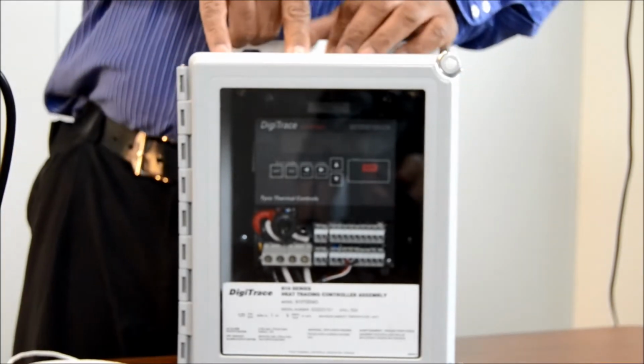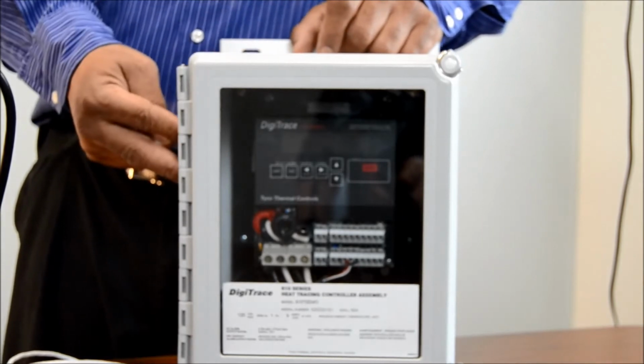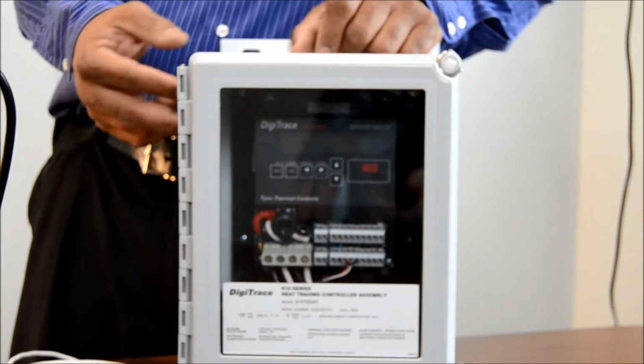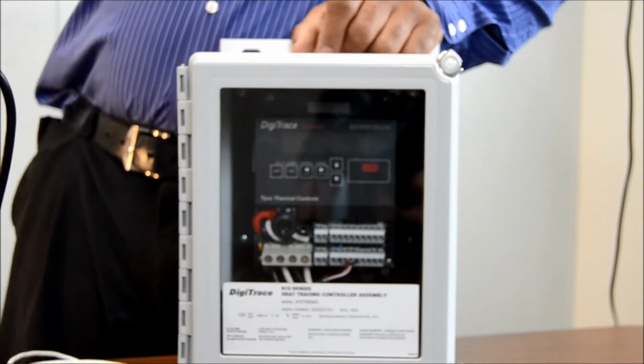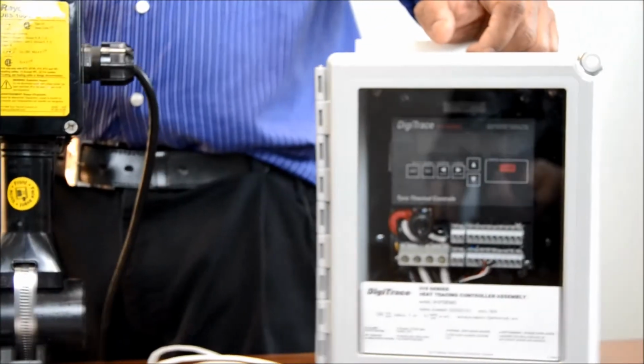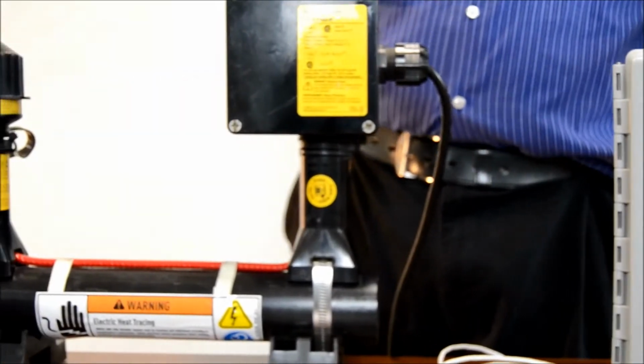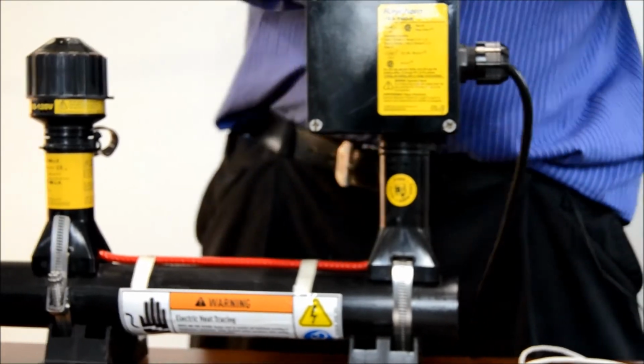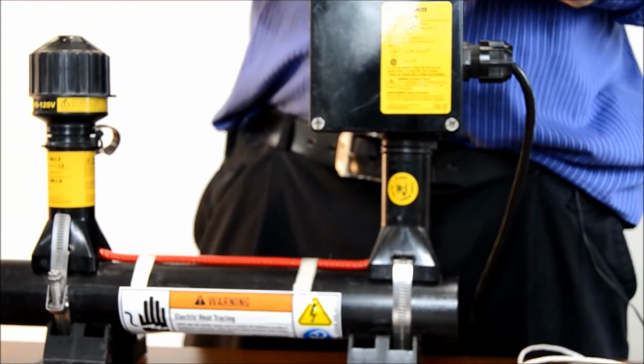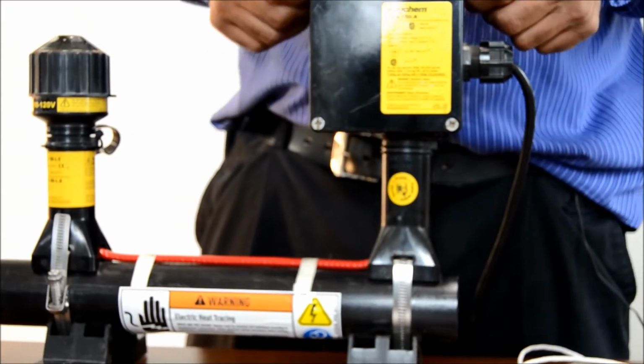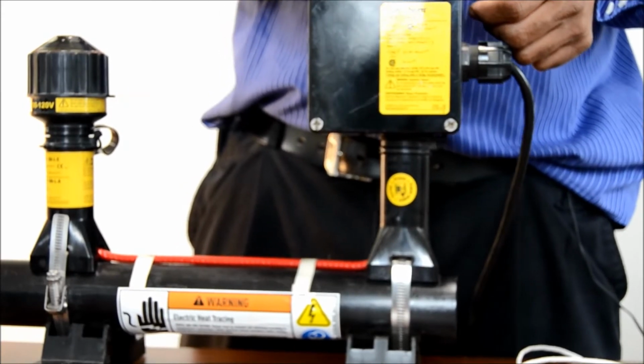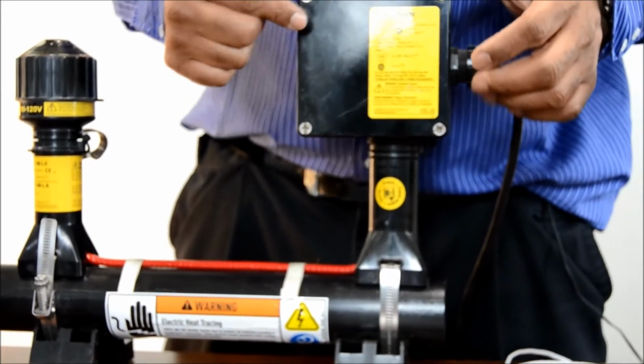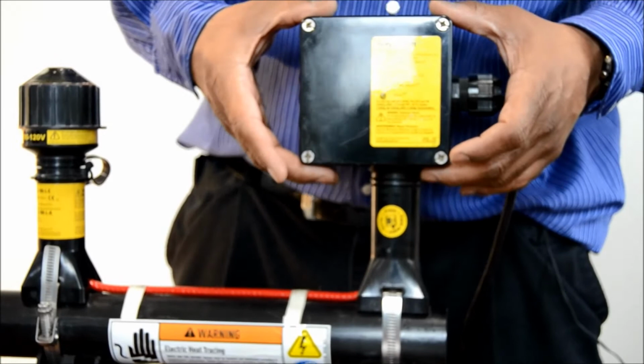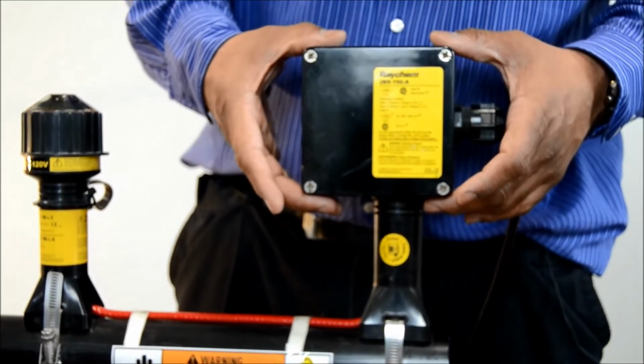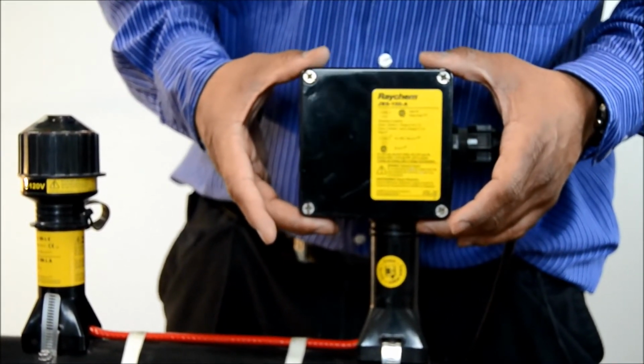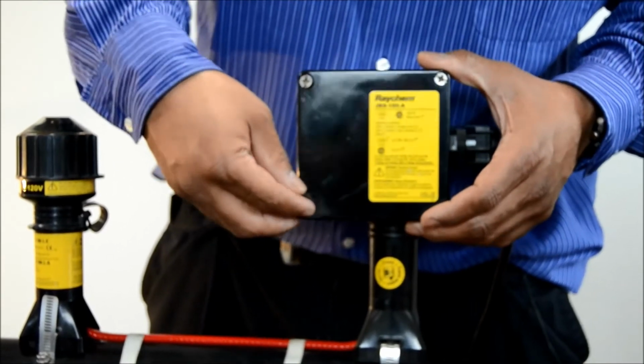Out of the 910 controller, you have electrical wires like THHN going into two of the JBS 100As, and this is a power connection kit. Anytime you have heat trace, you have to have a transition, and this serves as the transition.